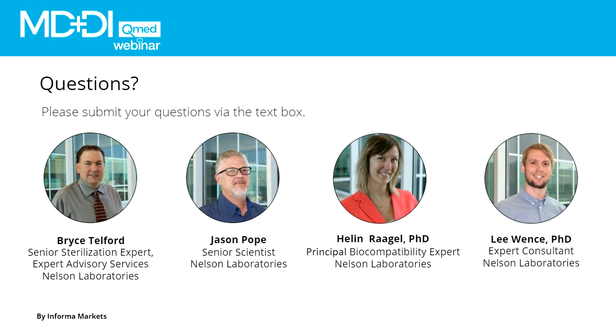Well, the thing is, cytotox results greater than 2 are a little bit more qualitative, compared to if you actually do an extraction on peroxide with a quantitative method, where you get an actual number for the concentration of residues on the device. So if you do have a failing cytotox result, doing the actual quantitative method on peroxide residuals can give you very good insight into why the device might have failed. Then you'll know whether it was due to the sterilization process. At least then you have some guidelines to either further pursue your cycle parameters, or, if it's not due to peroxide, to look elsewhere for that failure.